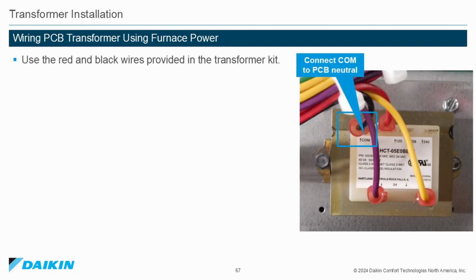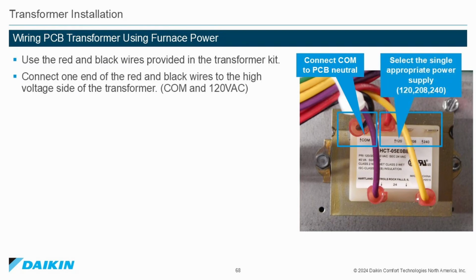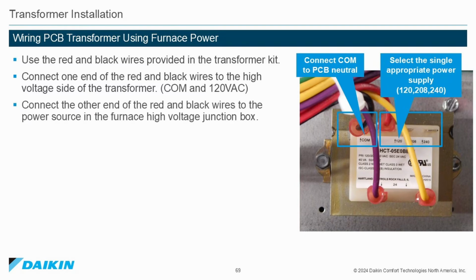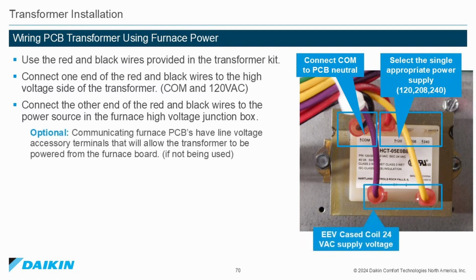Wiring the PCB transformer using furnace power. Use the red and black wires provided in the transformer kit. Connect one end of the red and black wires to the high voltage side of the transformer, common and 120 volt. Connect the other end of the red and black wires to the power source in the furnace high voltage junction box.